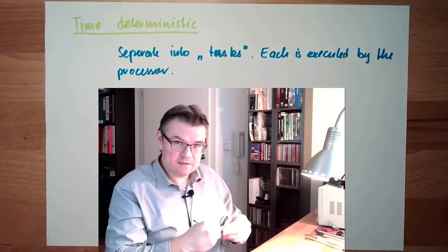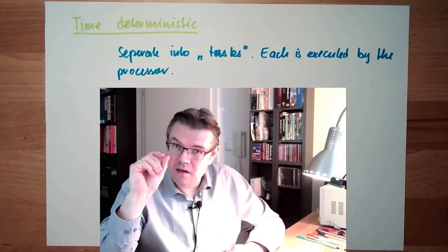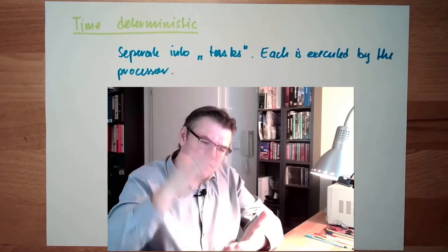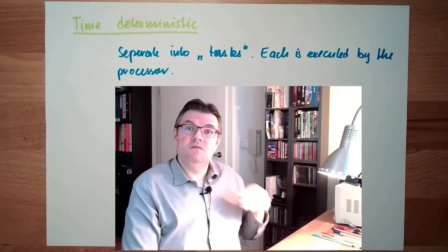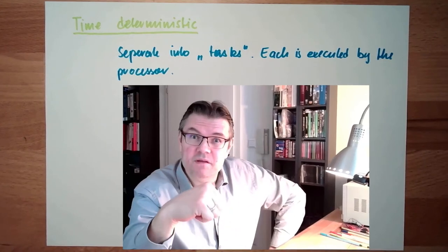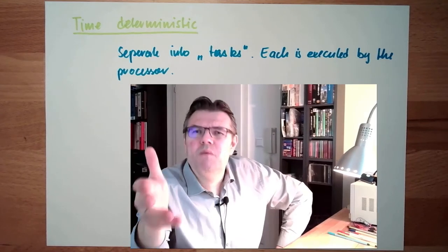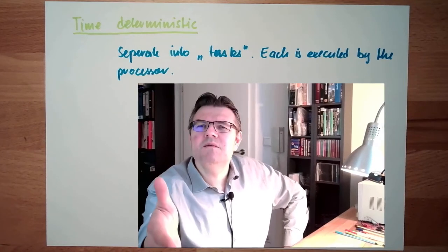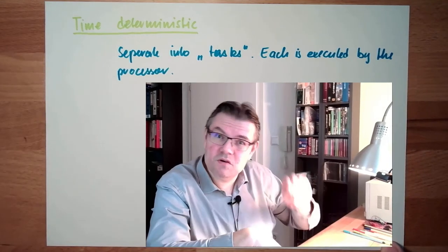If one of these tasks is blocking, there is also a stall time. If the stall time is reached and the task is not finished, the task will be cut and the next task will be executed. This means one task after another is executed. A task that is not running perfectly — due to a programming error, an unreachable sensor, or a communication issue — will simply be stopped.